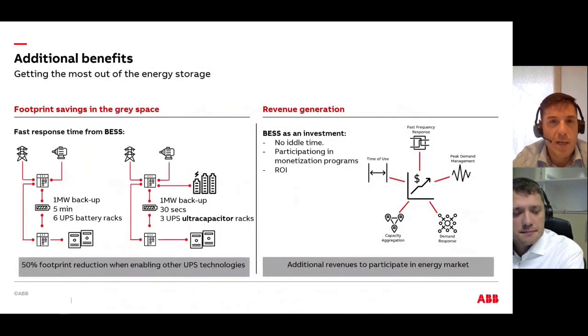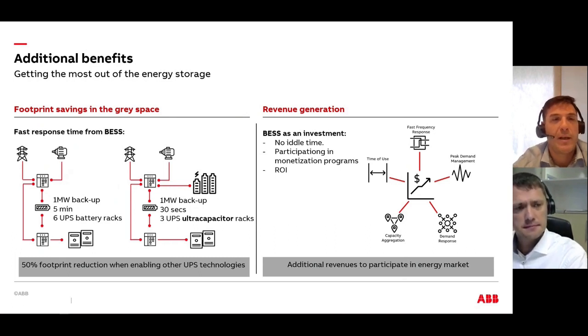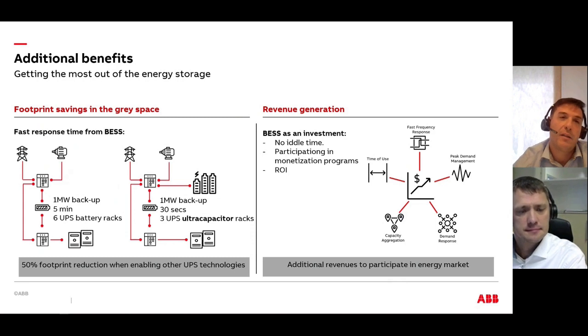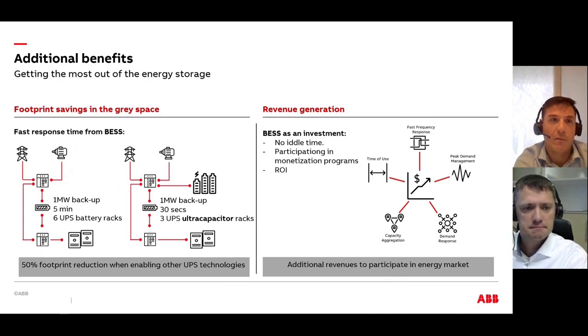So we have 2 use cases. One is to delay the start of the gensets. The other one is to replace gensets fully, but we have additional benefits, as I was pointing out before, when we have battery energy storage in our energy mix in the data center. One is the footprint savings in the grey space. If we consider today 1 megawatt of backup power, normally those servers will need 5 minutes of capacity installed in the UPS until the genset is up and running and online. We need mostly 6 UPS battery racks behind that in order to achieve that power and duration.